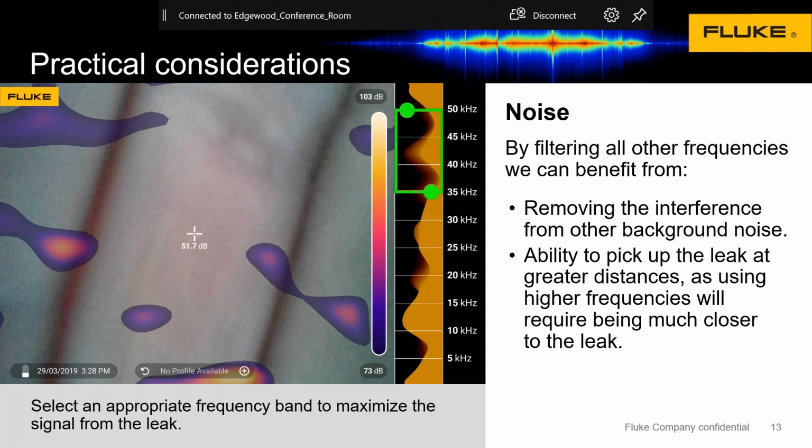If you have a whole area down in the sonic range, 20 kilohertz and below where we hear, and there's a whole lot of really loud machine noise, which has been very common in some of the plants I've inspected so far, don't put your filter right there. Put it a little bit higher up, all right? Get outside of the noise and ignore all the machine noise and listen for the noise of the leaks. So it's very, very simple to filter it, and it's also very simple to set up different preset settings on the ii900. So if you have different kinds of things you're looking for, different kinds of leaks, different parts of the factory, it's there, and it's a button press away, so you don't have to remember it.